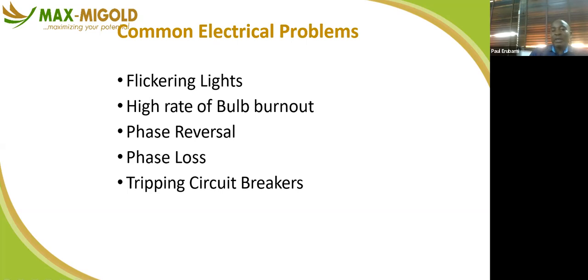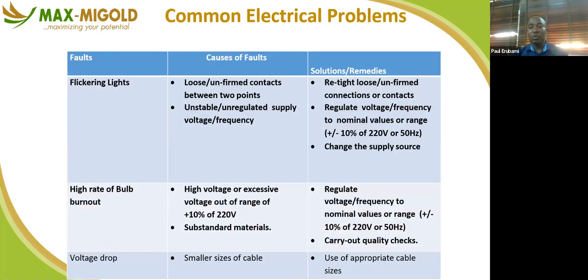So there are common electric problems we experience in our building facility management, mostly electrical. We have the flickering light, your bulb is burning out every now and then, phase reversal, loss of phase, and tripping circuit breaker. So when you experience this, in this table, you know what to do. It gives you a clue of what is happening and how to go about it. When you experience flickering light, there is either a loose connection or a poor contact between two points. What you do, you retighten. So this makes work easy for you. Unstable and irregular supply voltage and frequency: you regulate voltage and frequency to the normal value or range. So there's a standard which you can adopt. So your bulb is burning out every time.